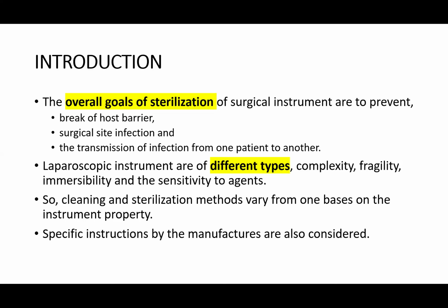Now, it is also important you take note of specific instructions by the manufacturer so that you use a proper agent in sterilizing this instrument and not causing corrosive damage that may lead to permanent damage to the instrument, or it may even obscure vision when the optical or objective lenses are affected. So specific instructions must be considered that are usually in the manufacturer's manual.